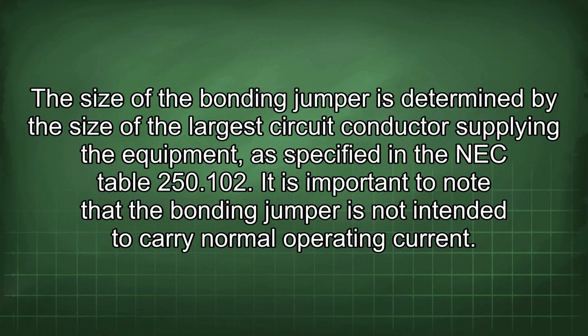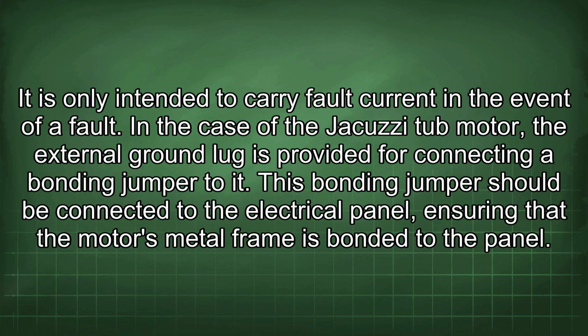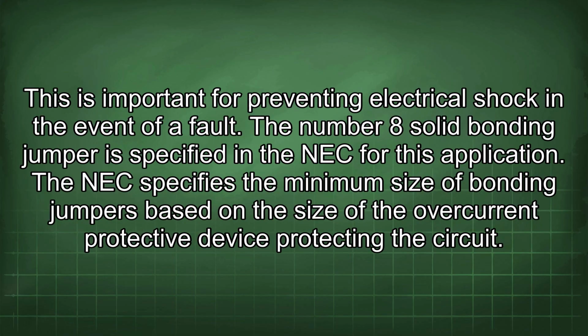The size of the bonding jumper is determined by the size of the largest circuit conductor supplying the equipment, as specified in the NEC Table 250.102. It is important to note that the bonding jumper is not intended to carry normal operating current. It is only intended to carry fault current in the event of a fault. In the case of the jacuzzi tub motor, the external ground lug is provided for connecting a bonding jumper to it. This bonding jumper should be connected to the electrical panel, ensuring that the motor's metal frame is bonded to the panel. This is important for preventing electrical shock in the event of a fault.